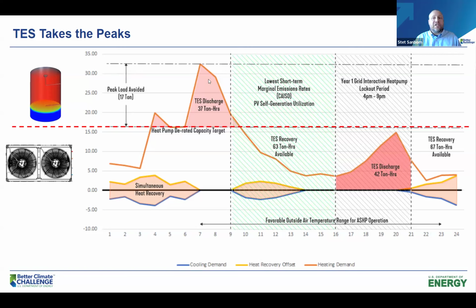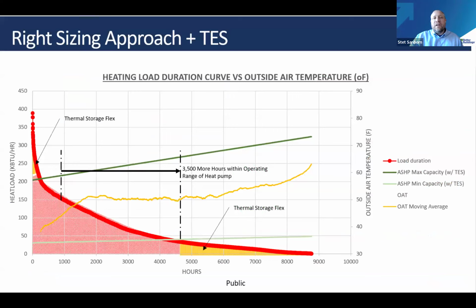So thermal energy storage gives you all the value of a battery without the chemical complexity, without the fire hazard, and it also lets you make the heat pump smaller. If I paired a heat pump with a battery, my heat pump would still have to be jumbo, but thermal storage lets me make that heat pump smaller. And I don't want to go too far into the weeds, but if anyone wants to nerd out with me at a conference on heat pumps and right sizing, I'm happy to.